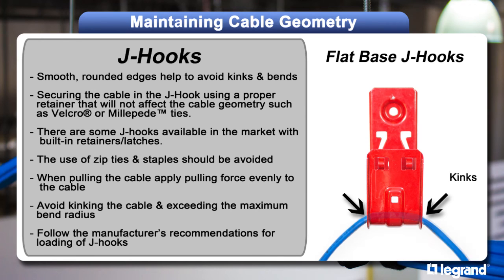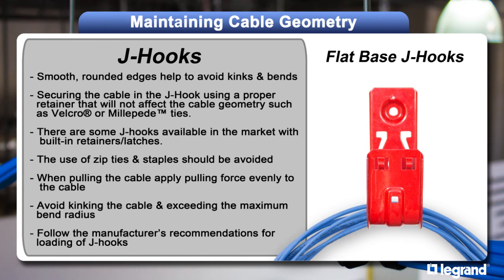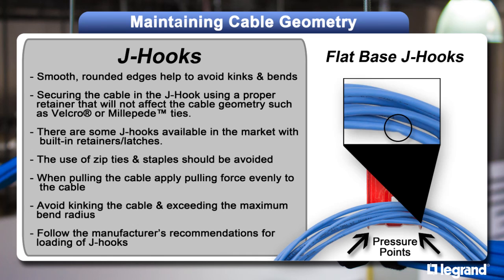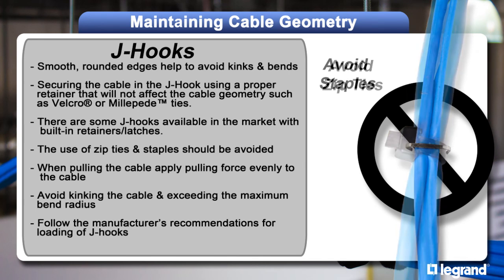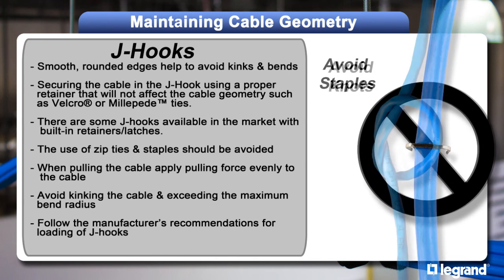A flat-based hook can create pressure points that can change the geometry of the cable. This is easier to see with a single cable versus a bundle of cables, but the pressure point is always there. When you bundle cable together, they have an inherent stiffness that tends to prevent tight turns, but not these pressure points. Avoid situations that tend to kink or change the geometry of the cable, such as tightly cinched cable ties, staples, or knots.